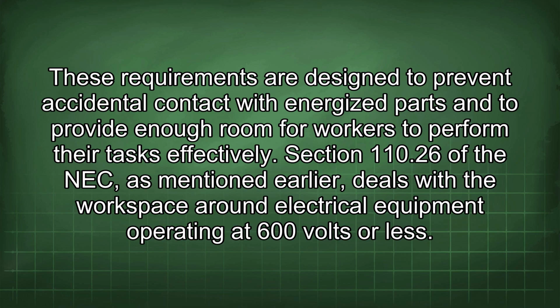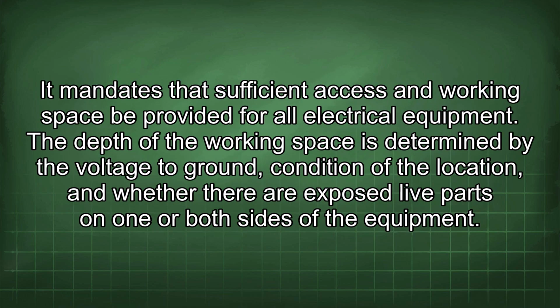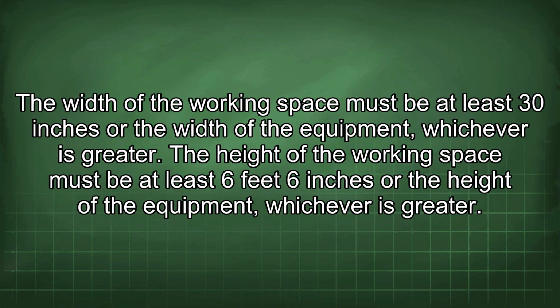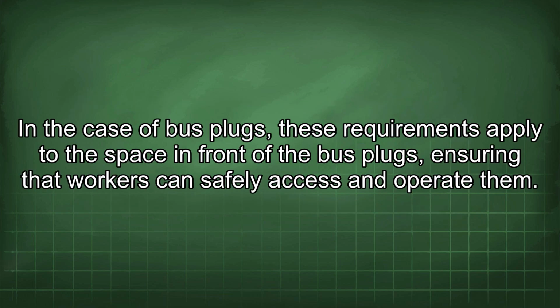Section 110.26 of the NEC, as mentioned earlier, deals with workspace around electrical equipment operating at 600 volts or less. It mandates that sufficient access and working space be provided for all electrical equipment. The depth of the working space is determined by the voltage to ground, condition of the location, and whether there are exposed live parts on one or both sides of the equipment. The width of the working space must be at least 30 inches or the width of the equipment, whichever is greater. The height of the working space must be at least 6 feet 6 inches or the height of the equipment, whichever is greater. In the case of bus plugs, these requirements apply to the space in front of the bus plugs, ensuring that workers can safely access and operate them.